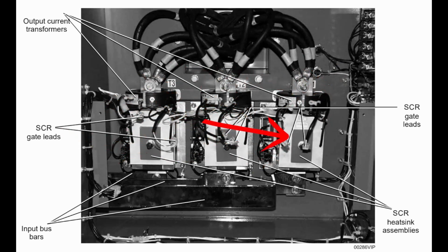So this is how we would cool a larger set of SCRs if these were to stay in the electrical cycle. So these are not meant to cycle over to electromechanical. These can stay in the cycle, and once they fully close, they're just closed. They don't do anything else. And over here, your positive and negative terminals are tied together internally. So unlike the other style I showed, they were separated into 2 different terminals because they're just using standard off-the-shelf SCRs. These are more specifically built for this application, to where internally here the positive and negative buses are tied together to rejoin our AC sine wave back together on the output side. And we have our line voltage coming in, but these can stay cool enough.